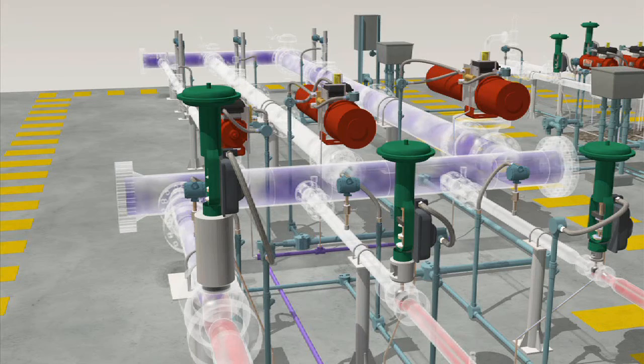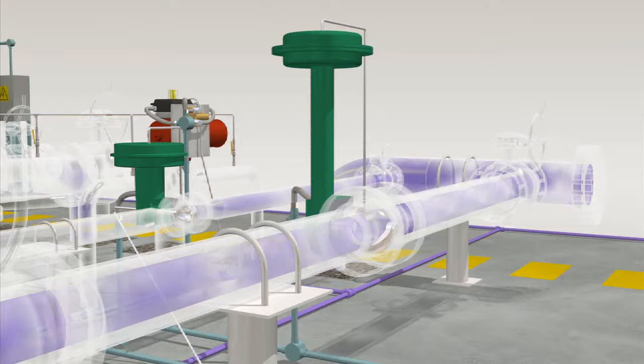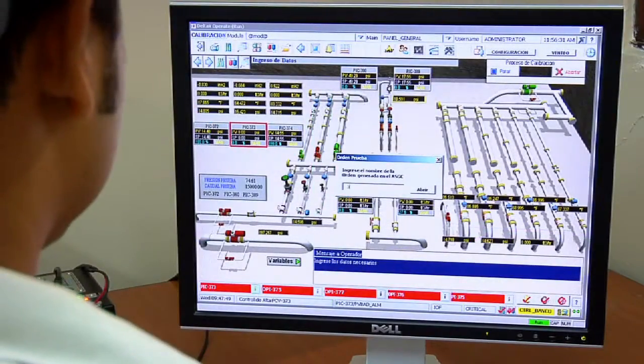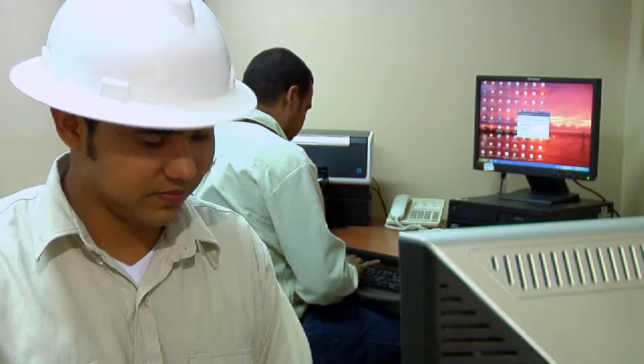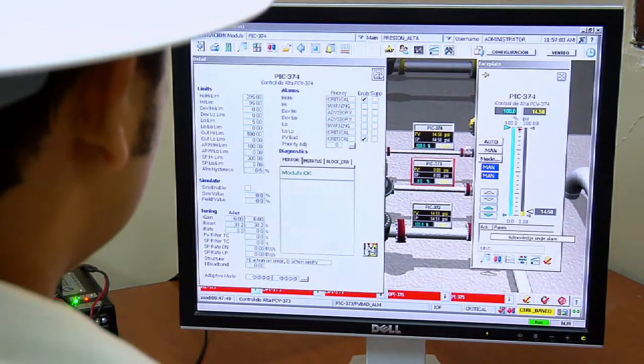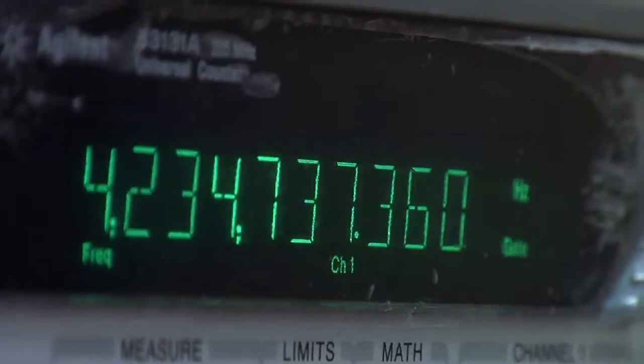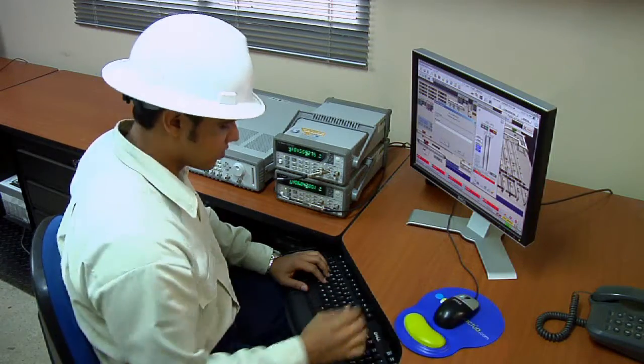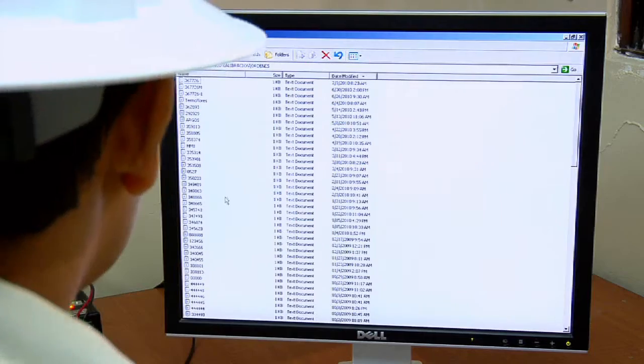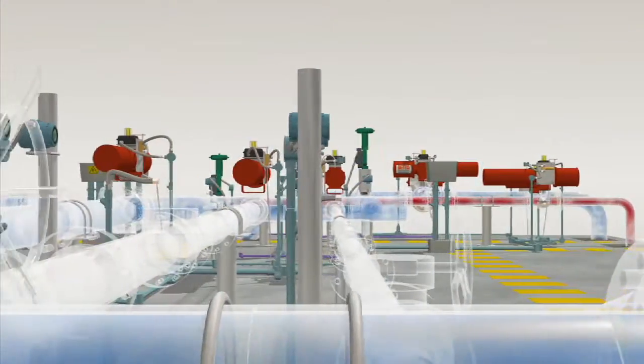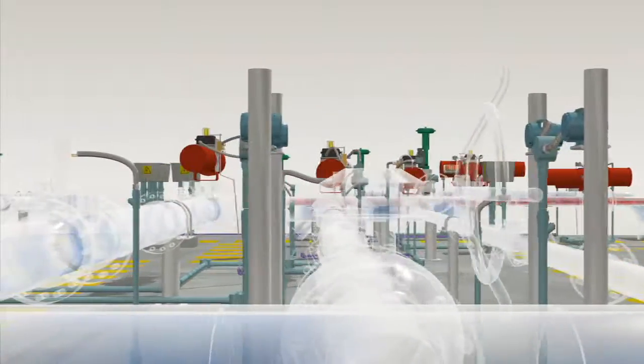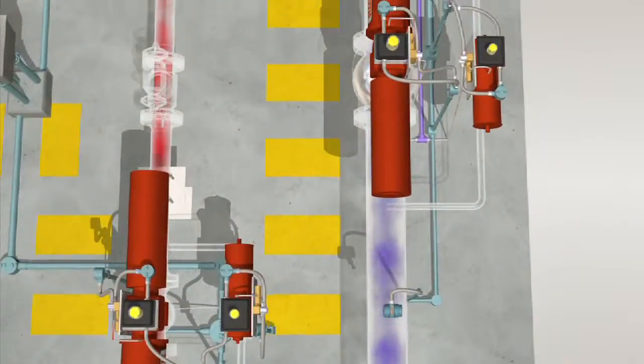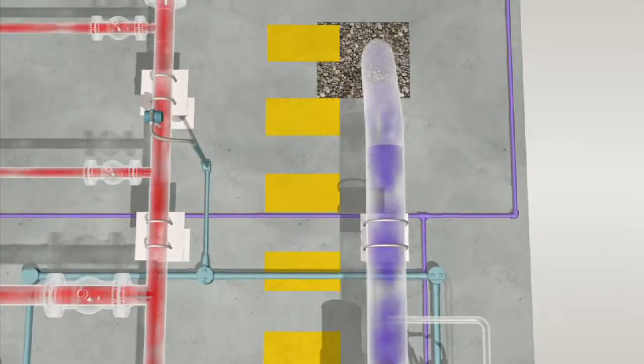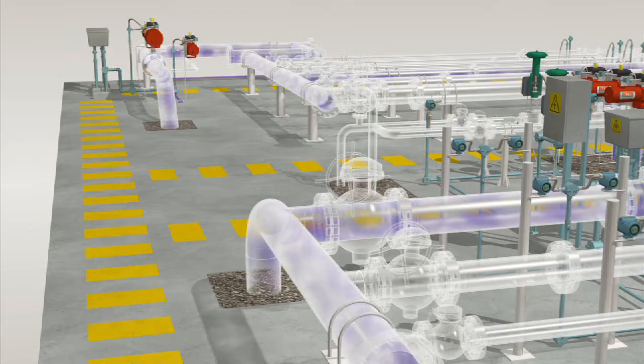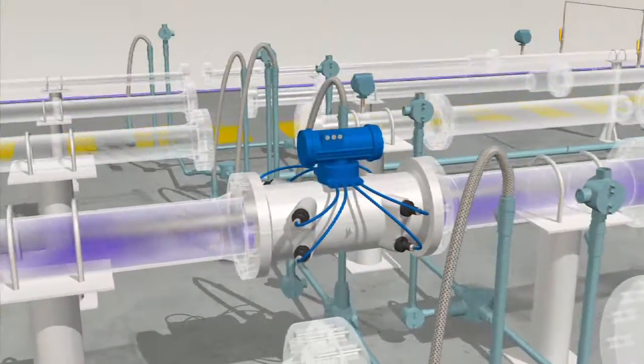The calibration process begins once the system is stabilized at the minimum flow. It consists of achieving and maintaining the different flow rates or calibration points under stability parameters. These points and the necessary number of repetitions for each one are determined by international standards and recommendations, best practices, or, in special cases, by the customer. Upon completion, the data acquisition system feeds the software for results analysis, which involves data validity verification and measurement uncertainty calculation for each calibration point. Finally, the software produces a calibration certificate.